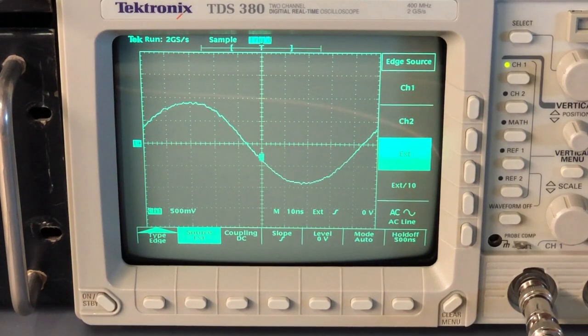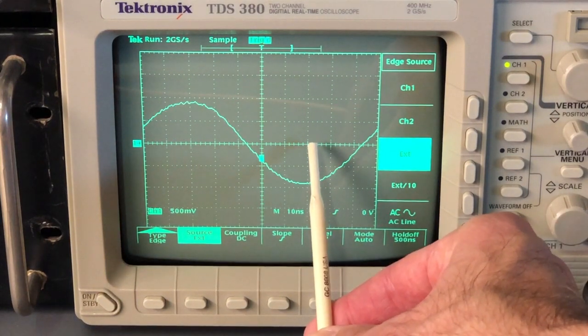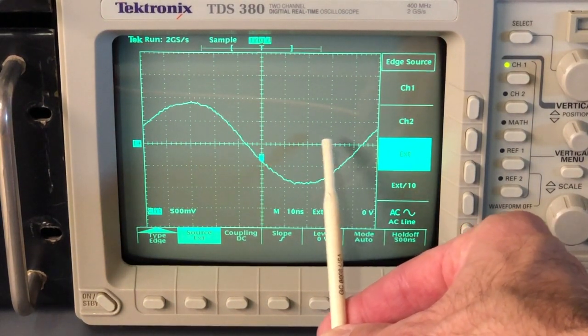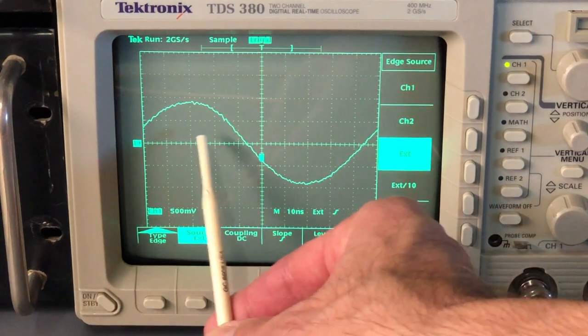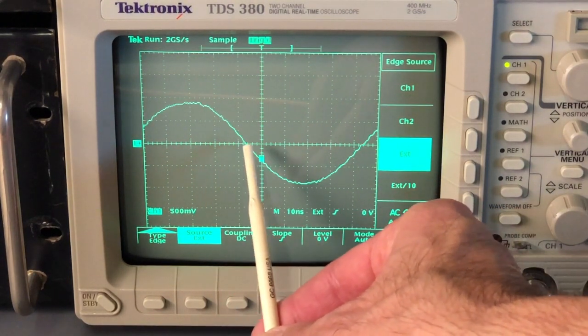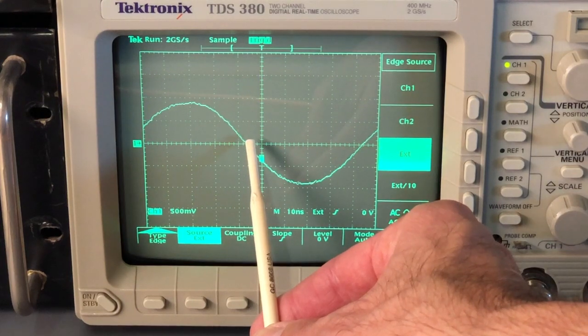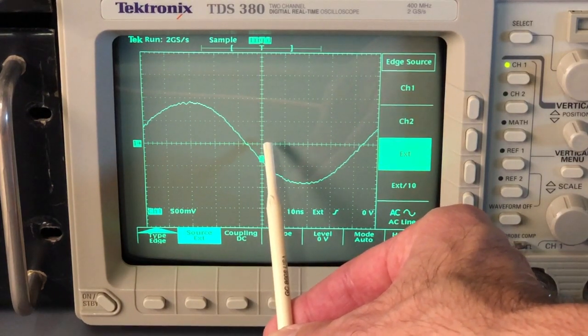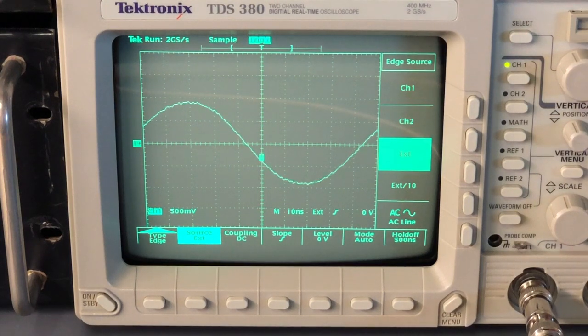So again, the service manual calls for, in 10 seconds, no more than 1 graticule of change or rolling or shifting on the waveform. So you could pick any of these graticules, but right here where the waveform crosses through, if you look at that, you would not want to see more than 1 graticule of movement in 10 seconds. Well, you can see that I've been talking for longer than 10 seconds and it hasn't changed hardly at all, very, very minimal amount. But we'll time off 10 seconds here and let's take a look at exactly how much movement there is in exactly 10 seconds. So we'll start now.